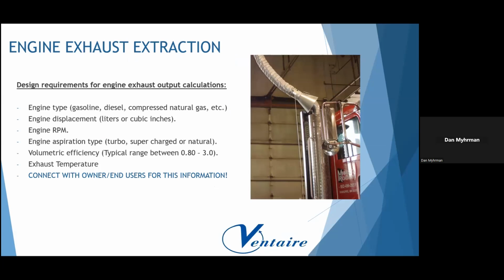When specifying vehicle exhaust extraction equipment, the biggest thing is to really connect with the owner and user to obtain this information. What you really want to find out is the engine type: gasoline, diesel, compressed natural gas, and the engine displacement. We want that in liters. We don't really need the horsepower. For instance, a 13-liter engine can put out anywhere from 500 horsepower to 750 horsepower. So displacement is key. Also the engine RPM that they're going to be running at while attached to the exhaust system. Aspiration: turbocharged, supercharged, naturally aspirated, volumetric efficiency, as well as exhaust temperature. And again, it's best to obtain this information from the owner and user so you're accurate from the beginning of the design.